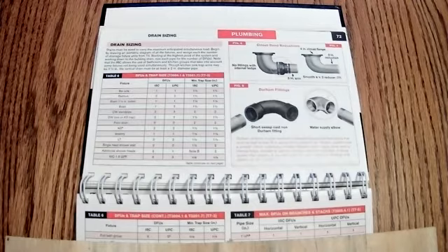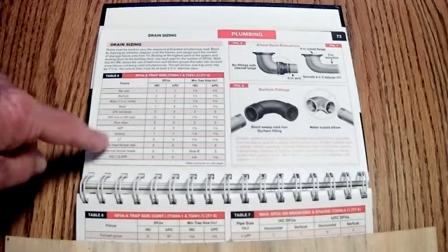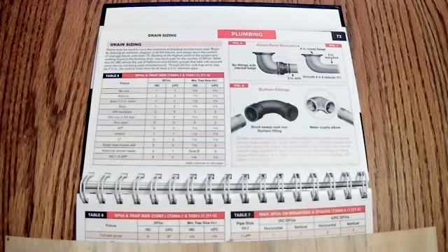All right. Drains must be sized according to their maximum anticipated simultaneous load. Begin with drawing an isometric design of all the fixtures and assign each of them a number of drainage fixture units according to table T6, which is right here. And again, starting at the highest point of the system, we're going to be working our way back to the drain, with each pipe size and the number of drain fixture units, or DFUs.